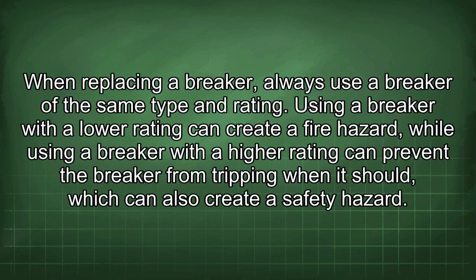When replacing a breaker, always use a breaker of the same type and rating. Using a breaker with a lower rating can create a fire hazard, while using a breaker with a higher rating can prevent the breaker from tripping when it should, which can also create a safety hazard.